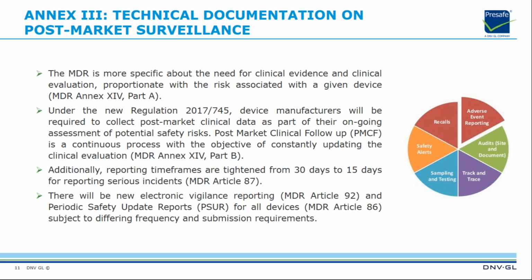Under the new regulation, MDR, device manufacturers will be required to collect post-market clinical data as part of the ongoing assessment of potential safety risk. Post-market clinical follow-up, PMCF, is a continuous process with the objective of constantly updating the clinical evaluation. So PMCF can be considered as part of clinical evaluation.